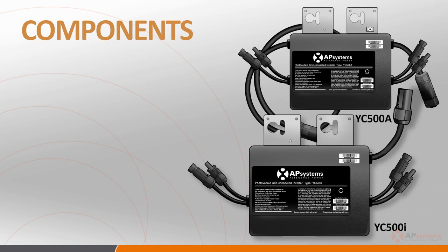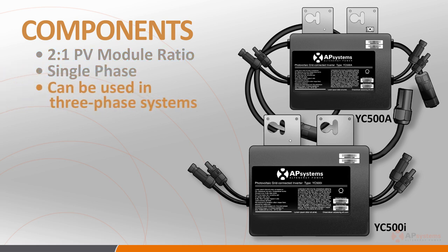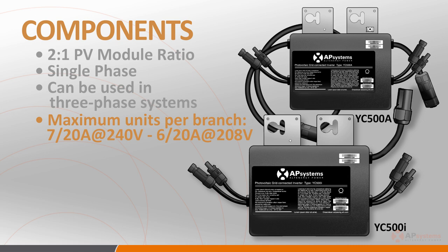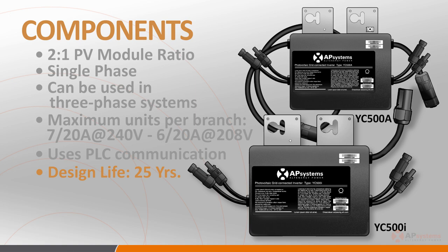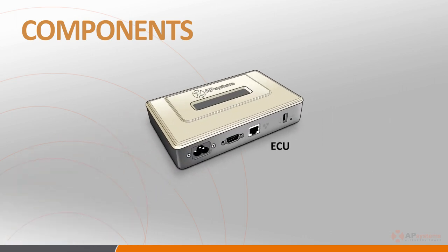The AP Systems YC500 functions as two inverters built into a single case. It's a single-phase inverter, but given its architectural flexibility, it can also be used in both 240-120 volt single-phase and 208 volt three-phase applications. The maximum number of units per 120-240 volt 20 amp circuit is seven, or a total of 14 PV modules, and the maximum number of units per a 208 volt 20 amp circuit is six, or a total of 12 PV modules. The YC500 uses the Power Line Communication or PLC protocol to communicate with the ECU, and it has been engineered for a design life of 25 years.